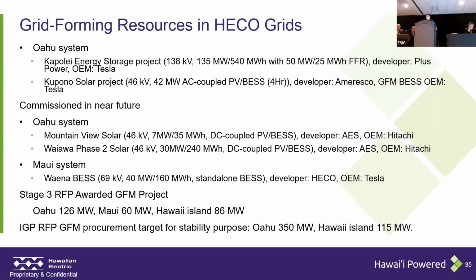The GFM projects that will be commissioned in the near-term future, which means next year or the year after next year, we have 2 more sub-transmission interconnected grid forming projects on the Oahu system. They are relatively smaller, 7 megawatts and 30 megawatts, this kind of size, and the developer is AES and the OEM is different. They're Hitachi GFM projects, and these two projects are DC coupled, DC coupled PV plus battery.